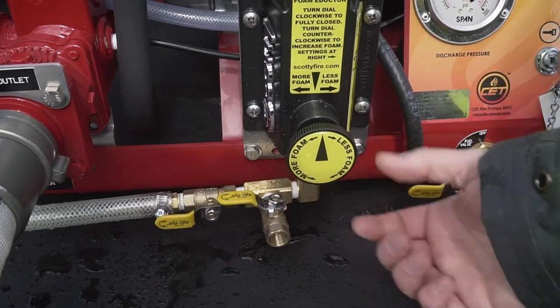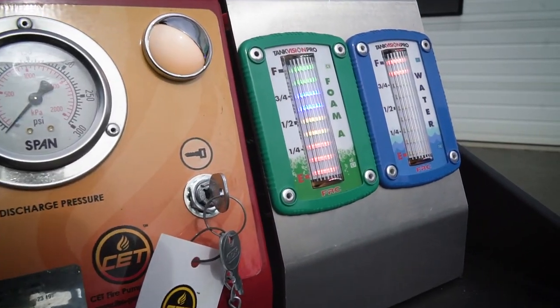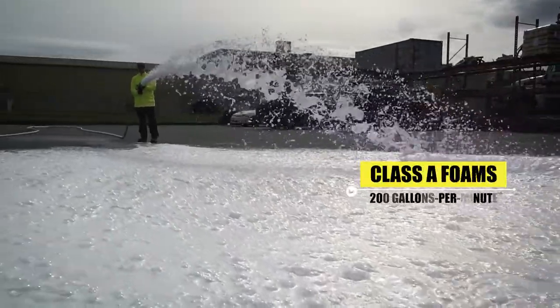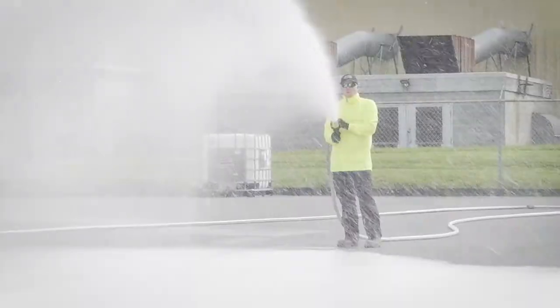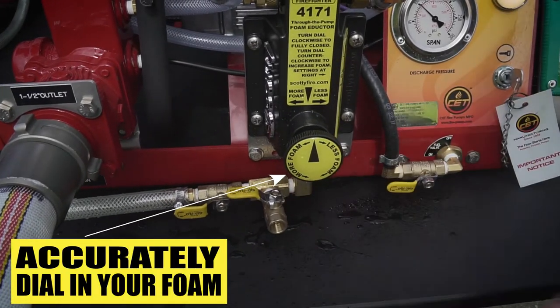The Scotty 4171 is capable of educting Class A or B foam concentrates — Class A foams up to 200 gallons per minute and Class B foams up to 95 gallons per minute. The 4171 is designed for a maximum operating pressure of 300 psi, and you can accurately dial in your foam using the Scotty 4171.